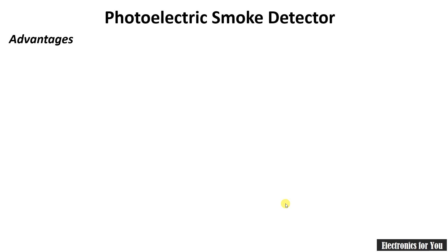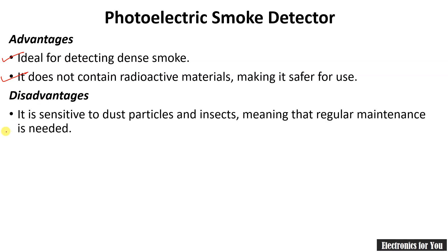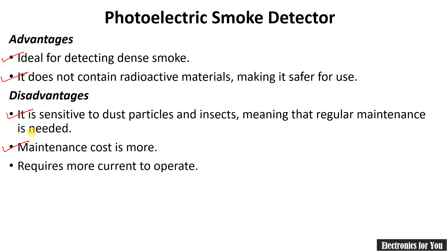The advantages of the photoelectric smoke detector are that it is ideal for detecting dense smoke and it does not contain radioactive material, making it safer for use. The disadvantages are that it is sensitive to dust particles and insects, meaning regular maintenance is needed, the maintenance cost is higher compared to ionization smoke detectors, and it requires more current to operate because the light source is continuously active.